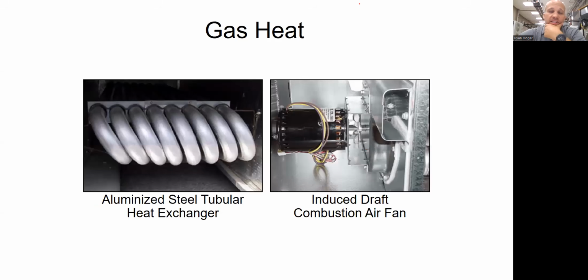From a gas heating standpoint, there are two types of heat exchangers that you typically would have on a gas-fired rooftop. You have an aluminum heat exchanger, and then you have a stainless steel one. As you might guess, the stainless steel one costs more, but it also lasts longer. In most applications, you get an aluminum heat exchanger because it costs less.